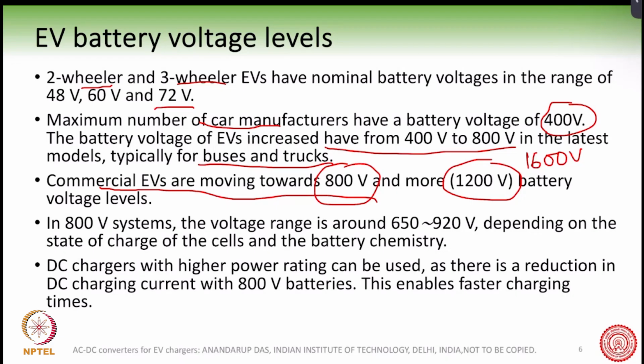One thing also to note is that for these 800 volt systems, the voltage of the battery can actually vary substantially, from 650 to 920 volt or even more. The 800 volt battery will have a higher voltage when it is fully charged and a lower voltage when it is fully discharged.